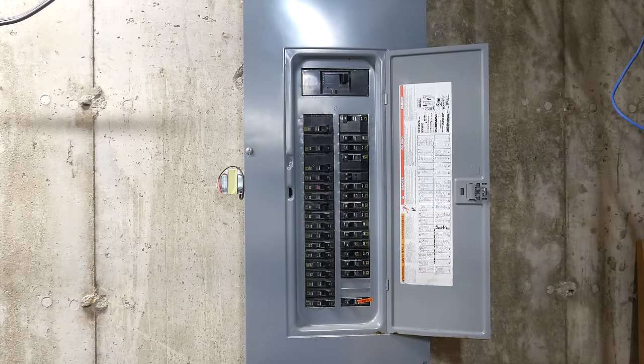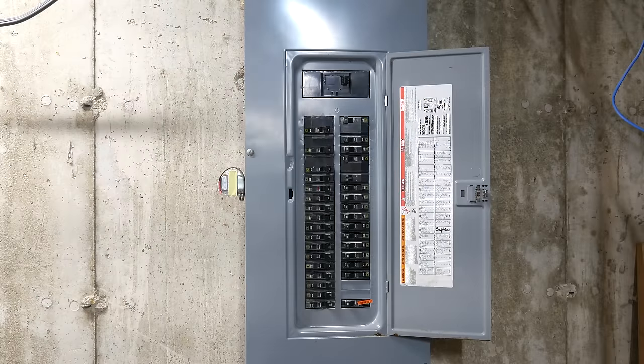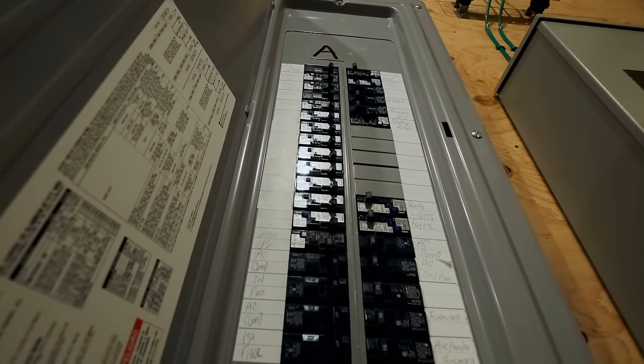Right now, your breaker box has one job: safely distribute power throughout your home. The main breaker keeps you from overloading the wires going into your house, and the other circuit breakers keep you from pulling too much power on the individual circuits they protect. Some might even offer arc fault protection and ground fault protection too. But that's it — it won't disable power to any circuits for any reason other than a fault. But what if it could selectively disable power to high-draw loads when required, and reconnect them later? Since all the power in your home goes through this thing, it could easily monitor which circuits are active and how much they are pulling. With some pretty simple programming, you could have such a breaker panel divvy up those 100 amps across devices, keeping you from ever exceeding the limit, and all while prioritizing active circuits so you don't even realize that's happening.